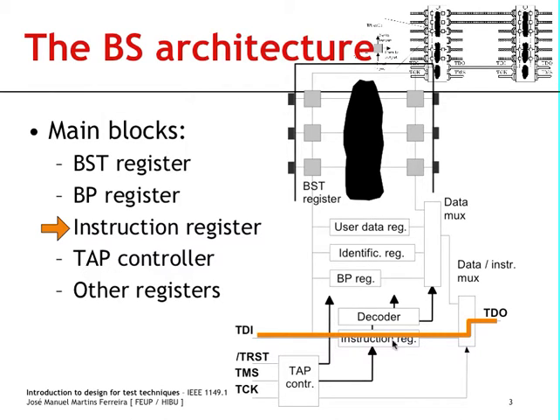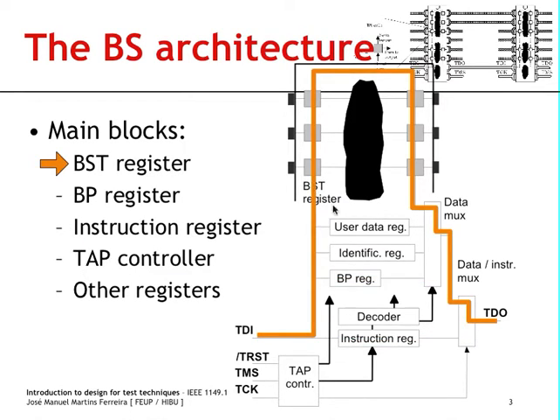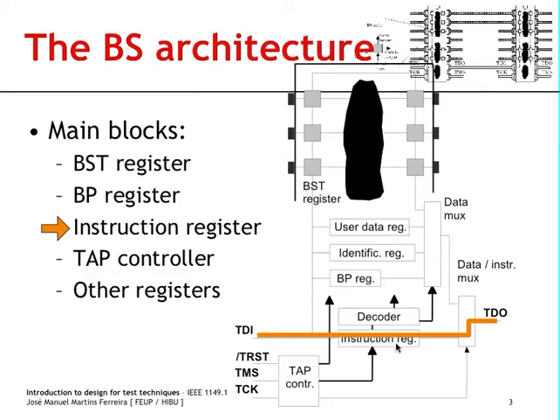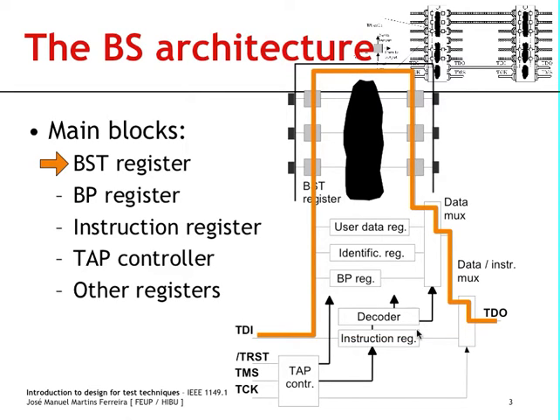The instruction register is the block where you will store the binary code controlling the data multiplexer. We will always have to start by shifting in a bitstream into this instruction register, and this bitstream — the instruction code — will define how the data multiplexer operates. So we can specify that we want the boundary scan register placed between TDI and TDO by shifting in an instruction that controls this multiplexer to operate as shown.